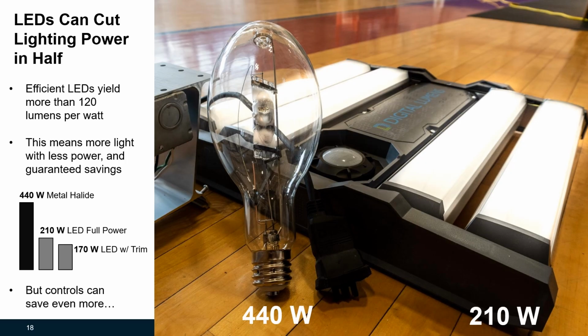Switching to LEDs can cut lighting power in half. The metal halides you see here used about 440 watts when they were on. The replacement LEDs used about 210 watts at full power. But the LEDs were too bright, so using task trim, we were able to reduce that power even further, trimming the lights to 80% brightness to match the UFC target spec. The LEDs were more than twice as efficient as the existing light sources.